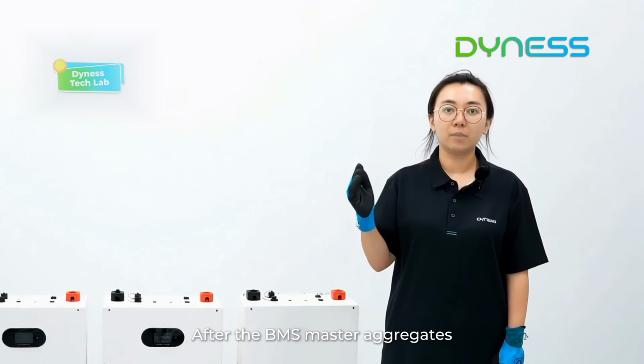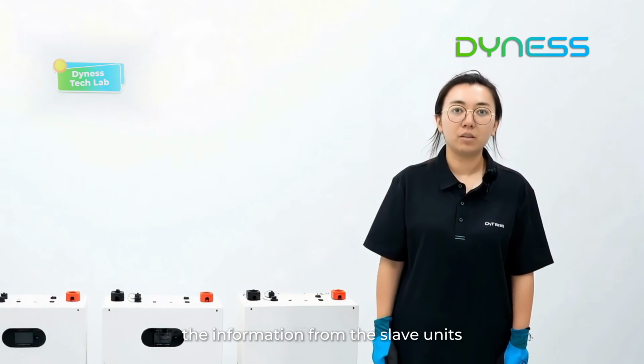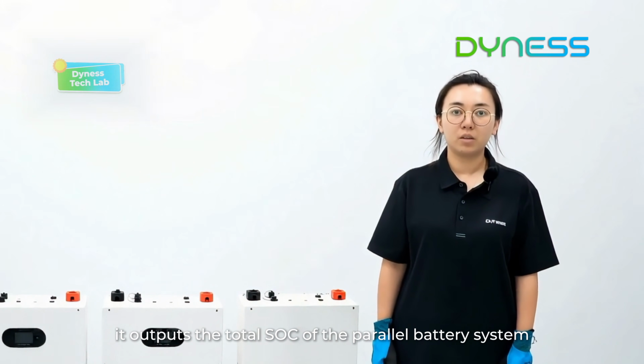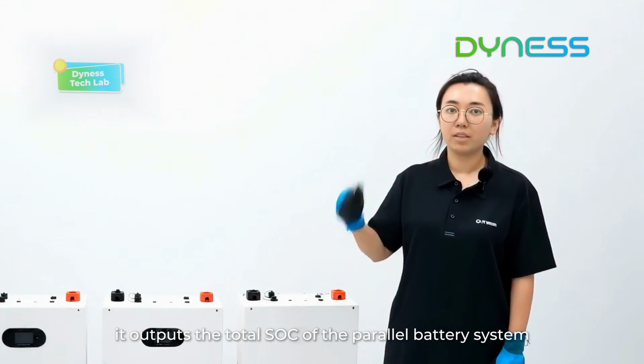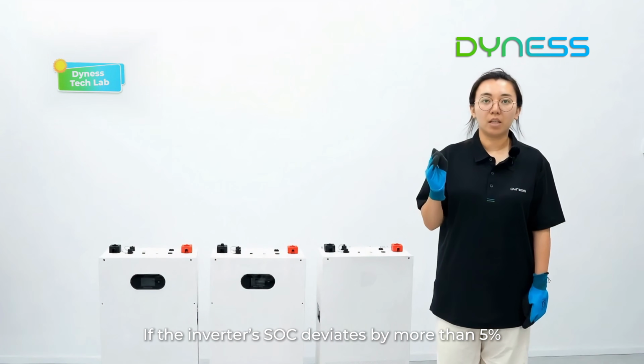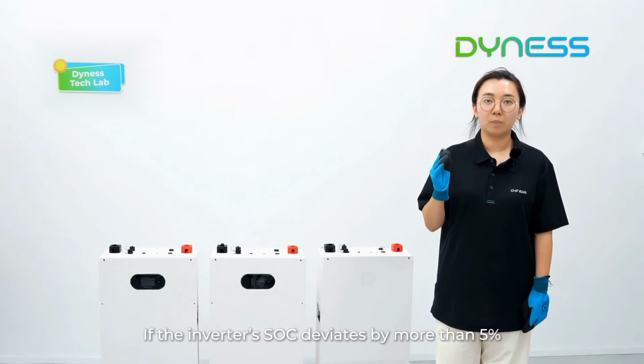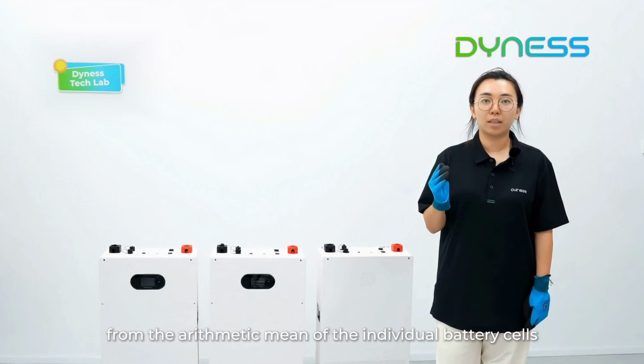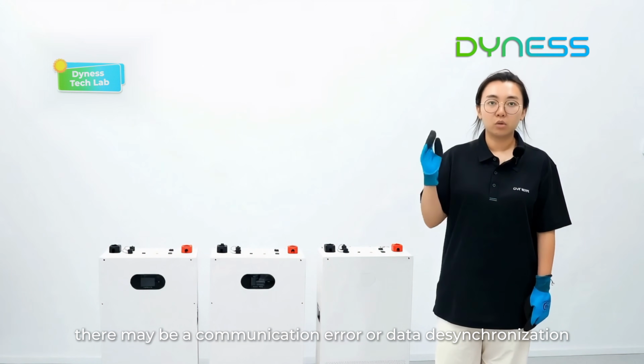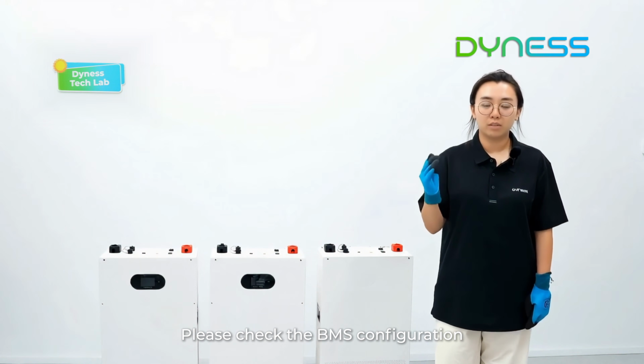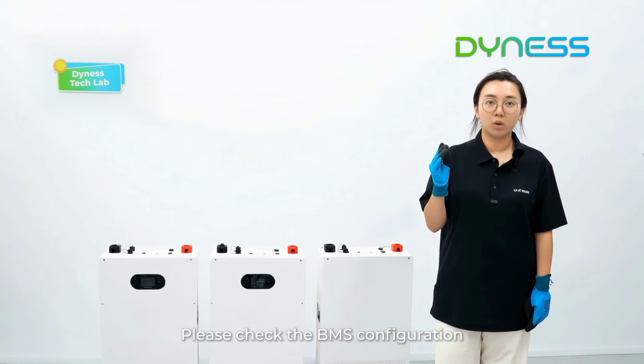After the BMS master aggregates the information from the slave units, it outputs the total SOC of the parallel battery system. Exception handling. If the inverter's SOC deviates by more than 5% from the arithmetic mean of the individual battery SOCs, there may be a communication error or data desynchronization. Please check the BMS configuration and communication connections.